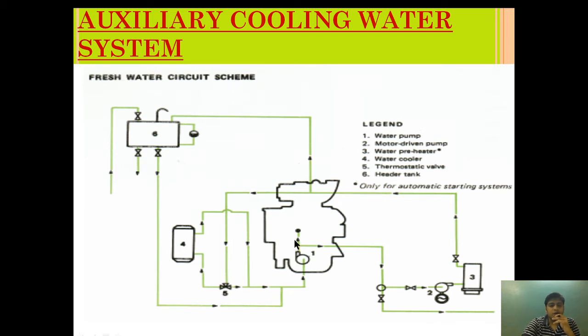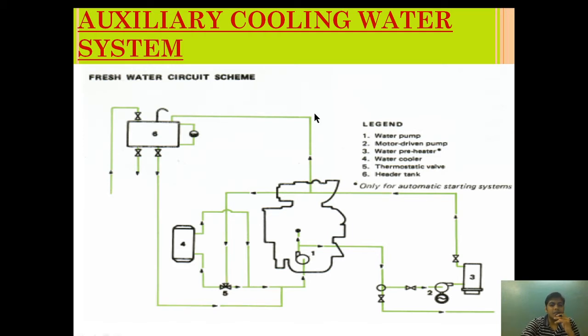While cooling, the water gains heat as it cools the jacket, turbocharger, and cylinder head. After cooling, the water returns and is fed to the pump, further heated, and sent to the mixing valve — and in this way the circuit continues working. The throttling of the three-way valve is controlled by sensing the inlet temperature; the valve bypasses the cooler depending on the temperature. When the engine is in standstill condition, the inbuilt heater is heated by steam to maintain the temperature and prevent thermal stress.